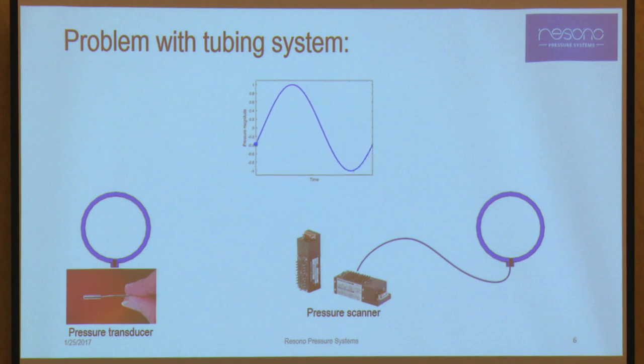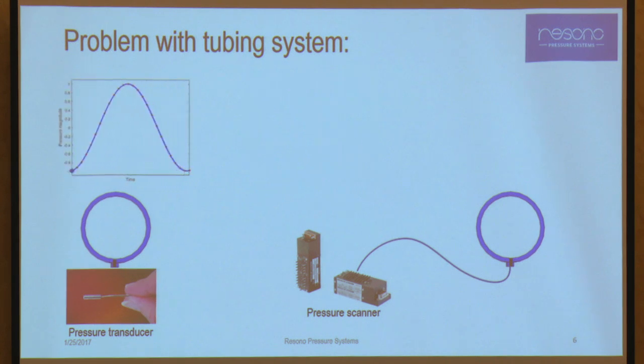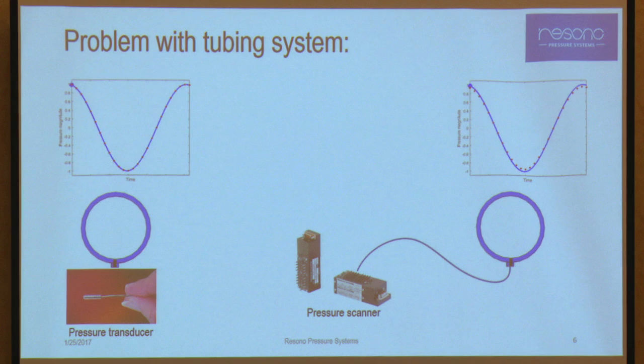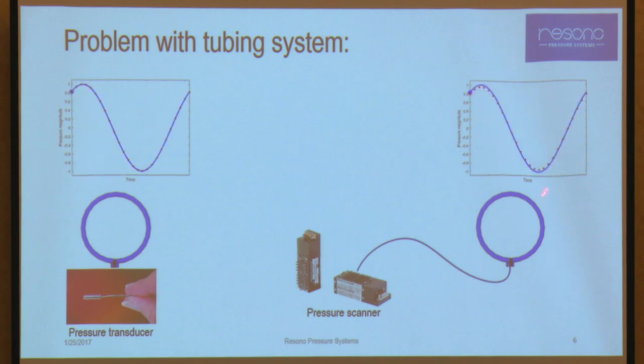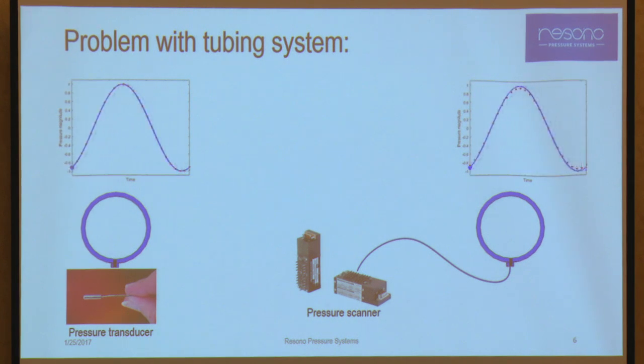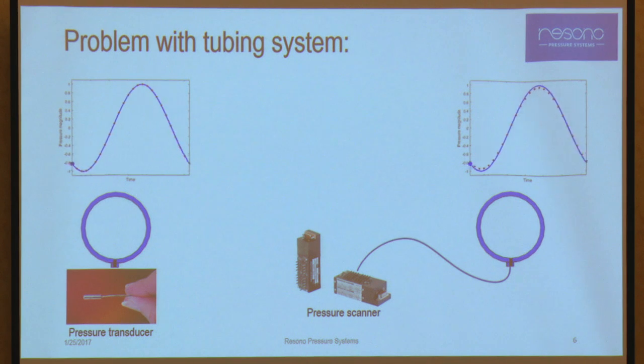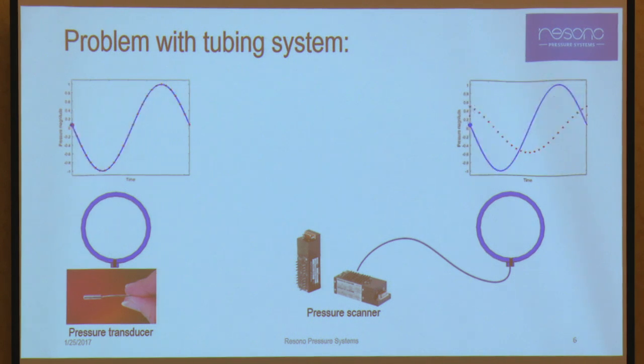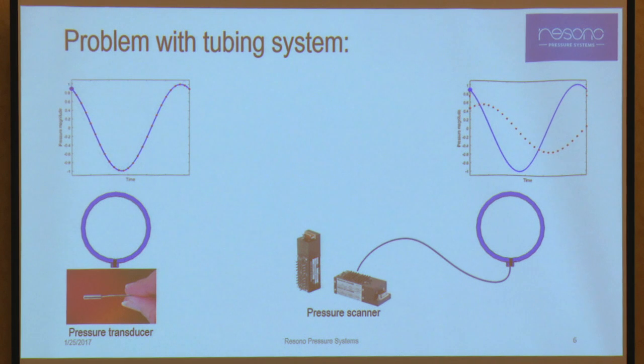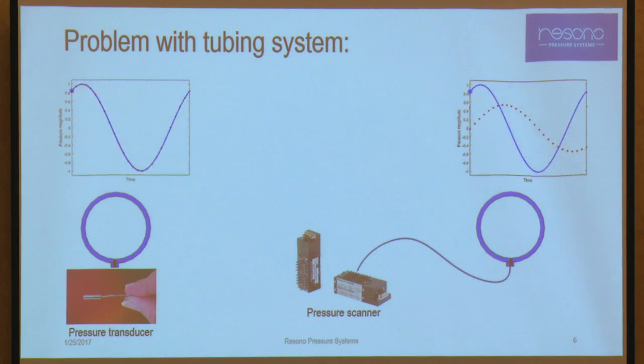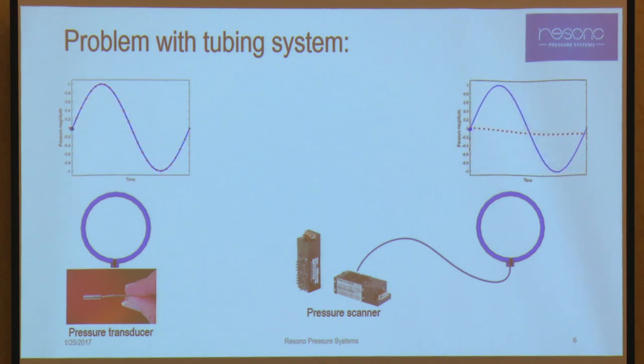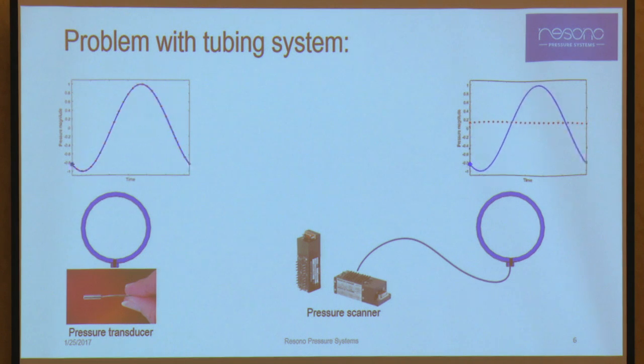I can use this transducer and be very accurate—there are little red dots here that are my measurements of that actual phenomenon. When I put a tube, I start seeing a little lag and amplitude attenuation in that signal, and as I go to longer and longer tubes, my measurements become essentially garbage. You cannot rely on those measurements.